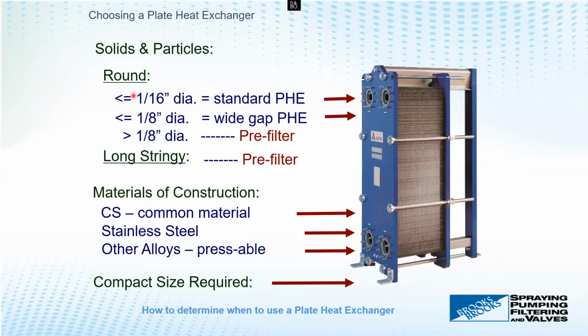Should we start getting a little bit bigger, essentially double that, we get to 1/8 of an inch diameter. We can now tailor the plate pack not only with corrugations, but make a wider gap between each plate, a little thicker, to allow these kinds of particles to fit through just fine. Again, we get nice long run time, preventing fouling, and the heat exchanger will run just fine.